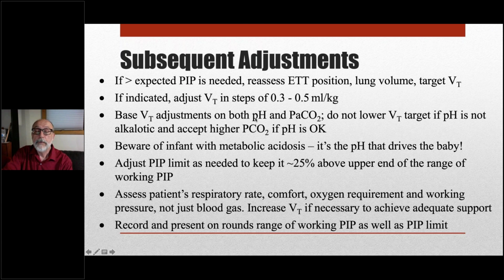Because babies hate to be acidotic. Permissive hypercapnia is something that doctors like, babies not so much. So we have to be careful and try to correct the base deficit in any way that we can, typically not with bicarbonate, but maybe some acetate in the TPN. You also don't want to keep the pressure limit way too high, because you want that feedback mechanism where, if something changes, the alarm will remind you that you need to come to the bedside and reassess the patient.